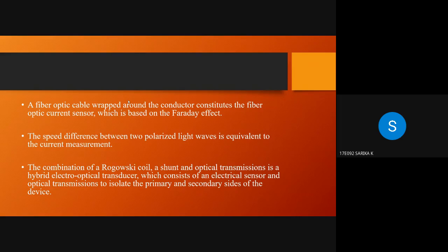The combination of a Rogowski coil, a shunt, and optical transmissions is a hybrid electro-optical transducer, which consists of an electrical sensor and optical transmissions to isolate the primary and secondary sides of the device.